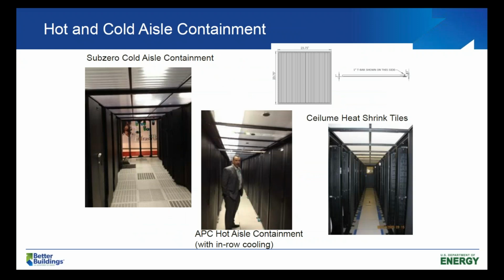So here are some more examples of containment. Here's a cold aisle containment with a hard lid and doors at the end. On the left side, there's a hot aisle containment. This is an APC arrangement with in-row cooling in lieu of CRACs or CRAHs. And then there are some heat shrink tiles on the right. That's where, if there's a fire in the space, they soften and drop out so that the fire detection and suppression system can function normally. Next slide.